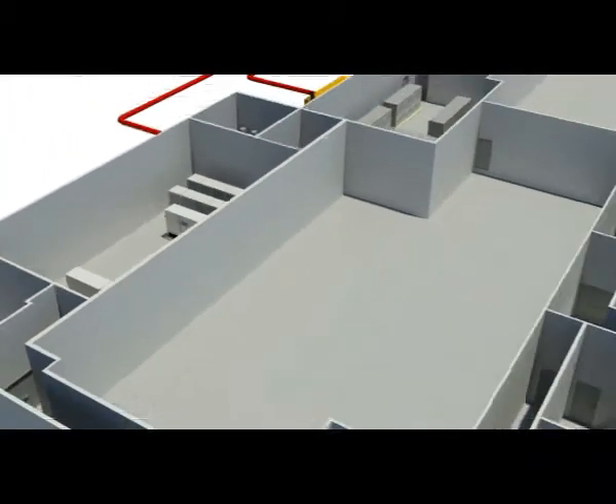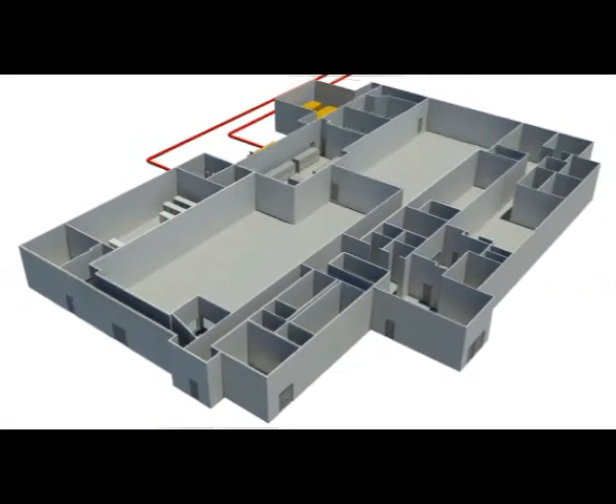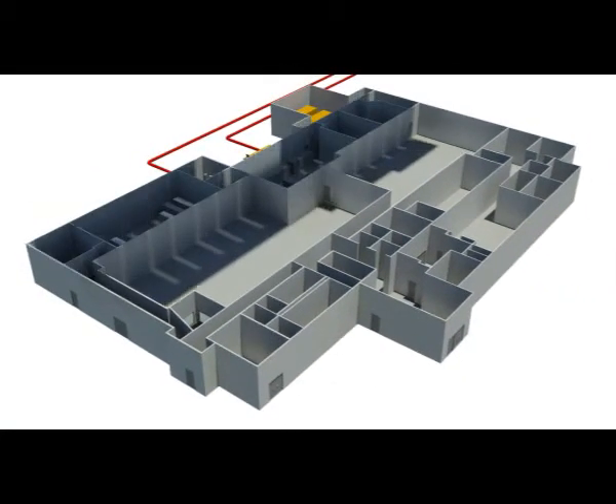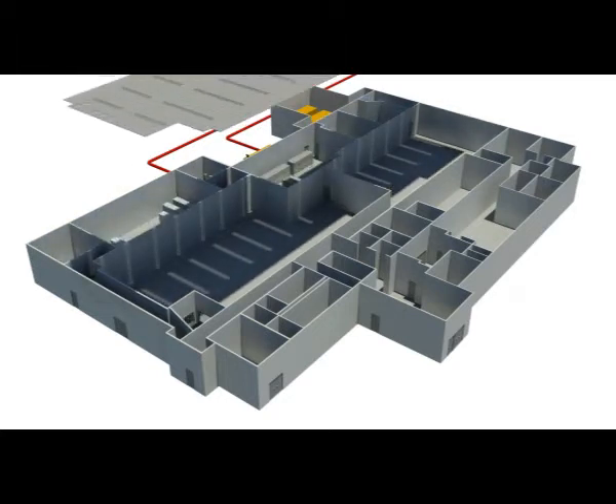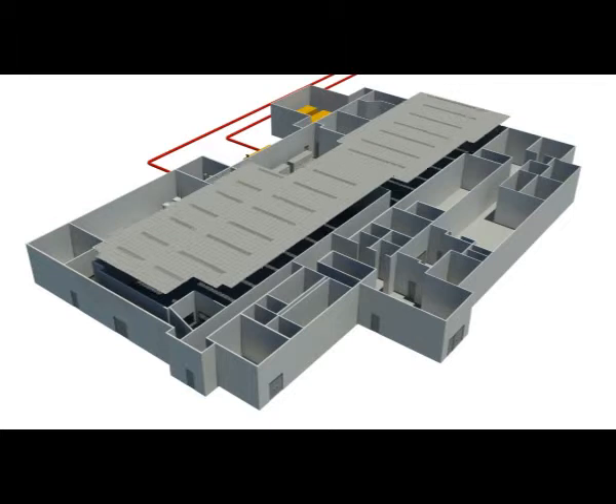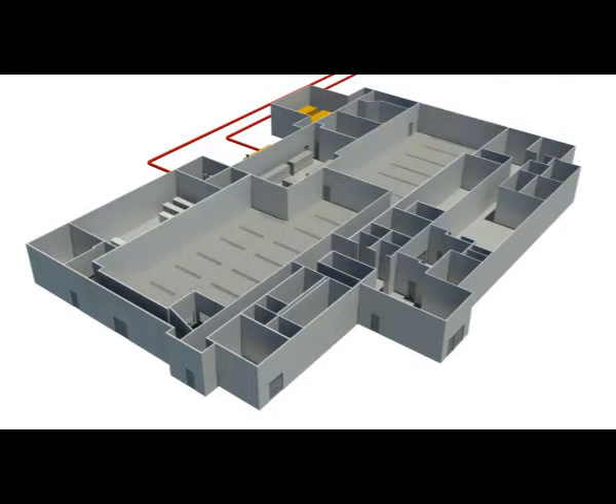The inside of the data center is intricately engineered to provide an optimal operating temperature at all times. 11,000 square feet of the total 22,000 square feet facility are engineered with 24-inch raised floors to circulate cool, temperature-controlled air into server rooms through floor-level ventilation systems. 21 redundant, high-capacity Liebert Deluxe System computer room air conditioner units with 450 tons of cooling positioned throughout the facility pump chilled air into the data room and keep hardware at optimum operating temperatures of 68 to 72 degrees Fahrenheit.